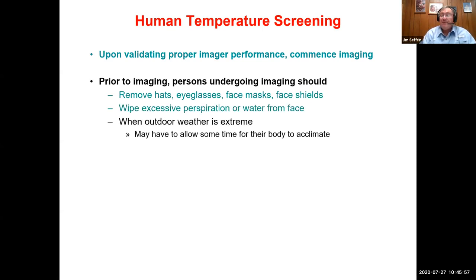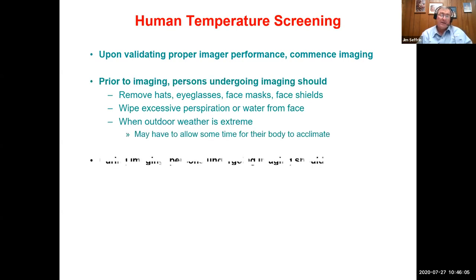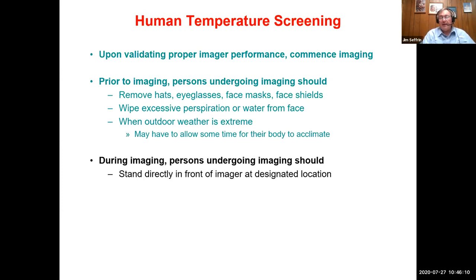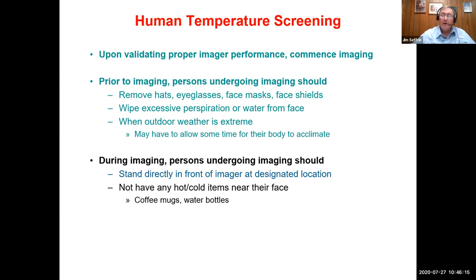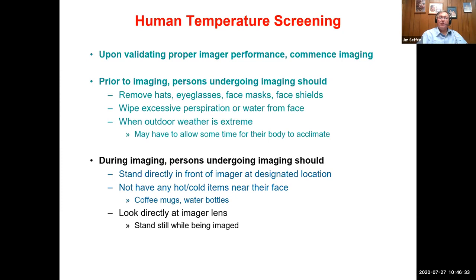When outdoor weather is extreme, you may have to allow some time for body temperature to acclimate, whether it be very hot outside or very cold outside. During imaging, persons undergoing imaging should stand directly in front of the imager at the designated location, not have any hot or cold items near their face, so no coffee mugs up near the face or water bottles. They should also look directly at the imager lens and stand still while they are being imaged. Fortunately, it only takes a second or two once they step up to the imaging spot, so it's not going to take a lot of time if they're properly prepared.